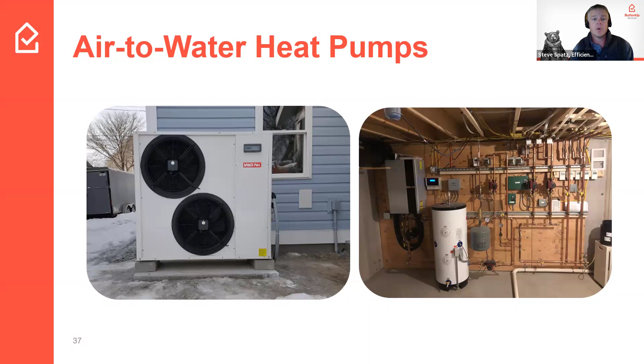So the outdoor unit, again, looks similar, if not just a little bit bigger than a ductless heat pump outdoor unit would. And then inside the building, that box that's mounted on the wall up there is where the heat exchange occurs from the refrigerant to the water. And then that tank right there is your thermal storage tank. That's what the heat pump is doing, it's maintaining a set temperature in that tank. And then that water from that tank is being sent out into the distribution system throughout the home. So this is a whole house system versus the individual room type system you'd be looking at with a ductless or a compact ducted heat pump. So you can do your whole home.